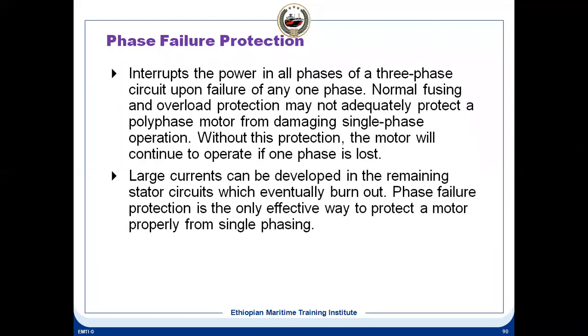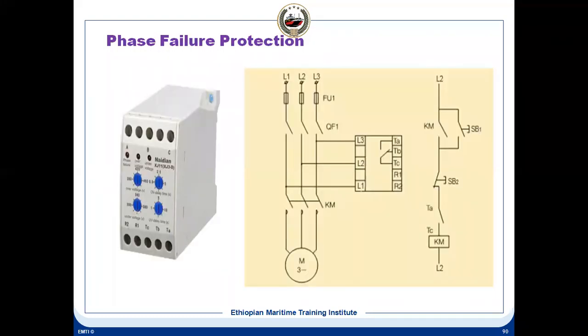Phase failure protection is very important. You can see in this diagram what a phase failure relay is. This is the relay on your left side, and on the right side is the inside connections. This relay has connections L1, L2, L3, which come from a three-phase supply.